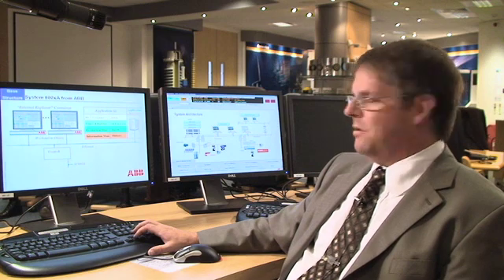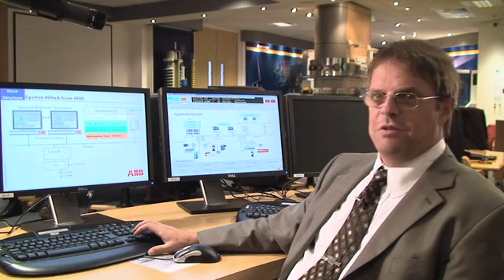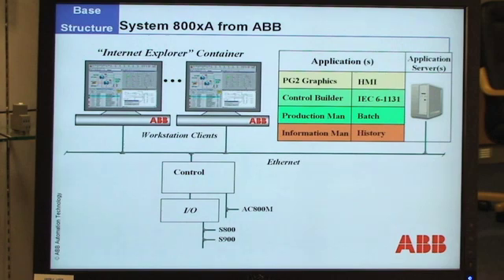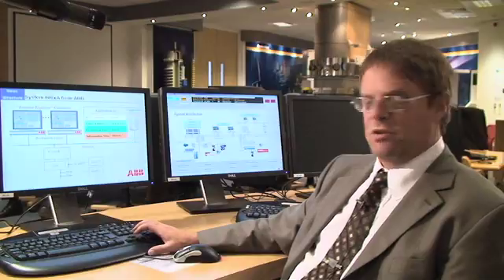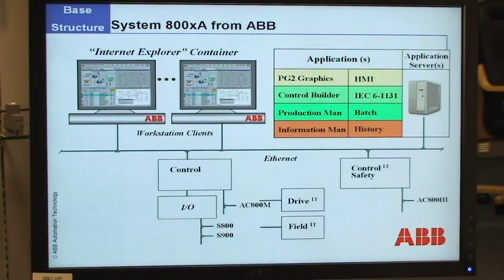We then need to add the control, so we select the controller which links into the standard Ethernet and we use the 800M controller of the size relevant for the application. We select the suitable I/O for the suitable industry and area — S800 or S900. We then determine whether we require fieldbus connectivity using Profibus, Foundation Fieldbus or HART, whether we want connections to drives and motors via Profibus or Optical, and whether we want a control application in SIL 3 and select the safety controller.